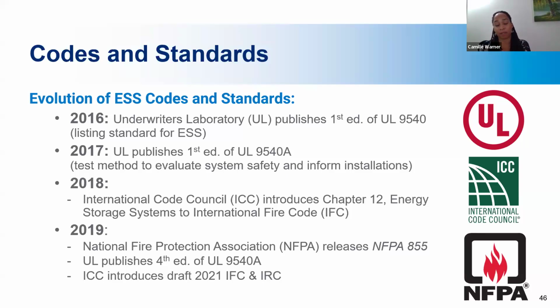In 2018, the International Code Council introduced Chapter 12 on Energy Storage Systems to the International Fire Code, which was exciting. In 2019, the National Fire Protection Association released NFPA 855, the standard for installation of energy storage systems. That same year, UL published the 4th edition of UL 9540A. Again, that's a destructive test, not a pass or fail; it just tells you here are the results, here's what happened.